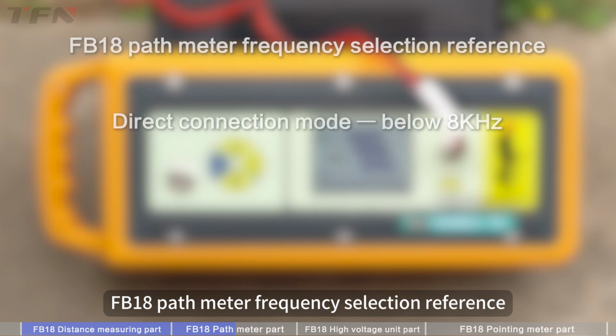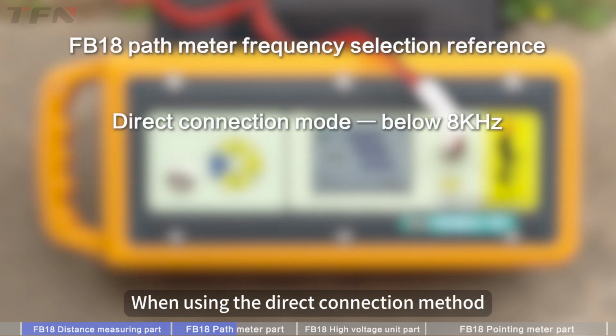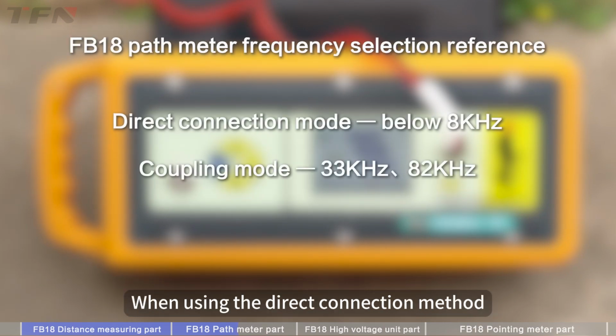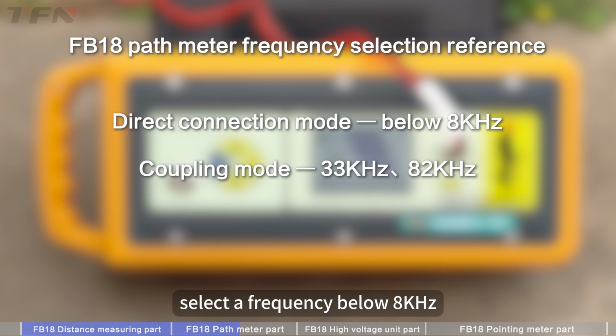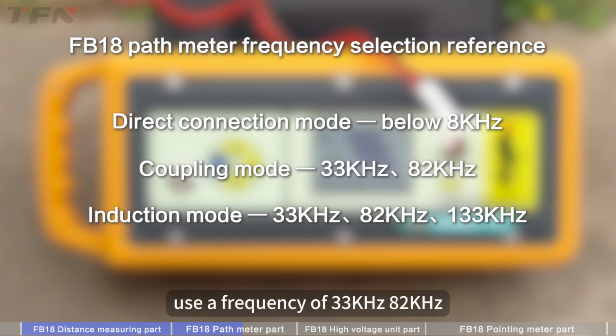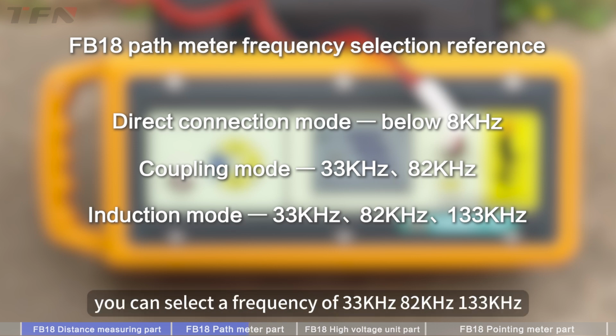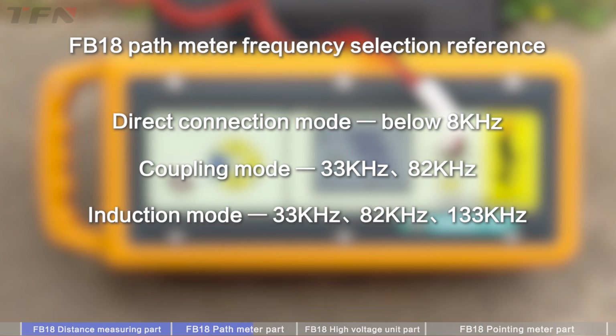FB18 path meter frequency selection reference. When using the direct connection method, select the frequency below 8,000 Hz. When using the coupling method, use a frequency of 33,000 Hz or 82,000 Hz. When using the induction method, you can select a frequency of 33,000 Hz, 82,000 Hz, or 133,000 Hz.